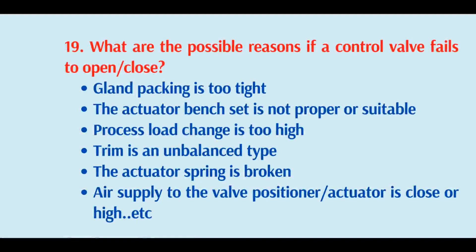What are the possible reasons if a control valve fails to open or close? Gland packing is too tight, actuator bench set is not proper or suitable, process load change is too high, trim is an unbalanced type, actuator spring is broken, or air supply to the valve positioner or actuator is closed or too high.